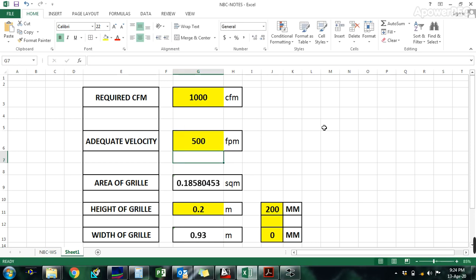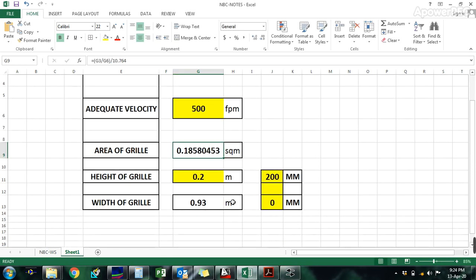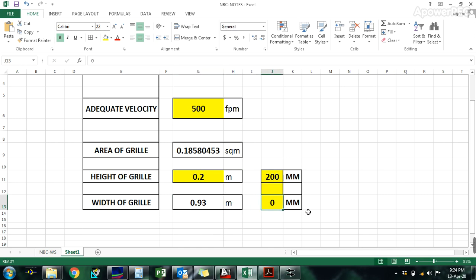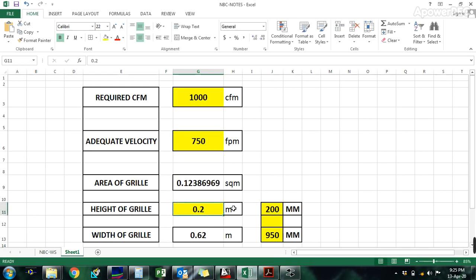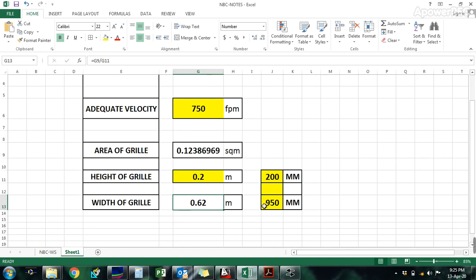At 500 FPM, the area comes out to 0.18 square meters. I have fixed the height of the grill at 0.2 meters, i.e., 200mm. So the width comes to 0.93, which means approximately 950mm. So a grill size of 200mm × 950mm is required. If fixed at 750 FPM, width is 0.62, giving 200mm × 650mm.